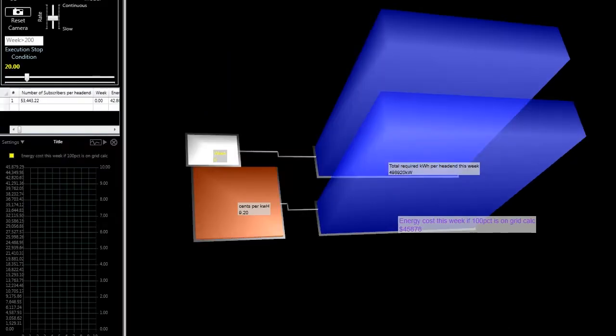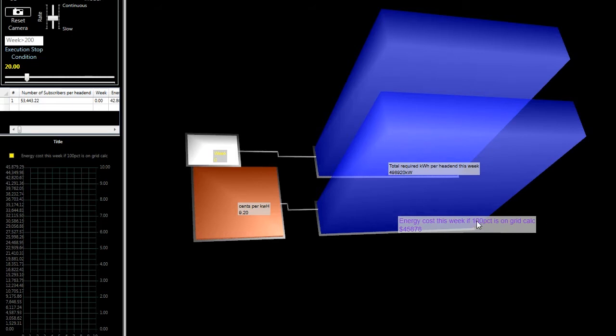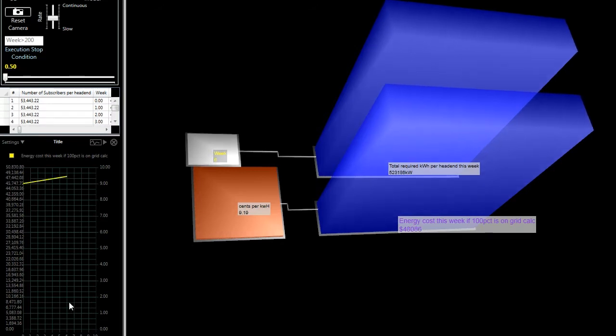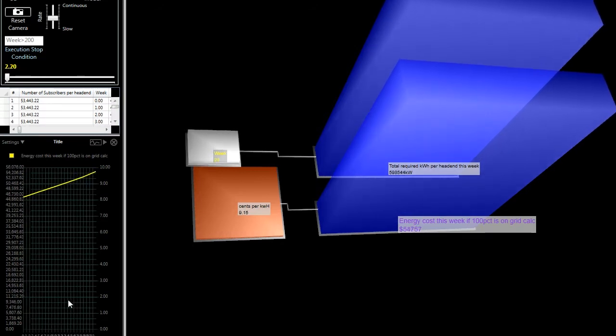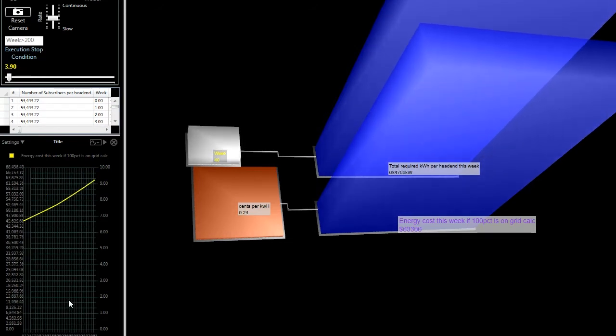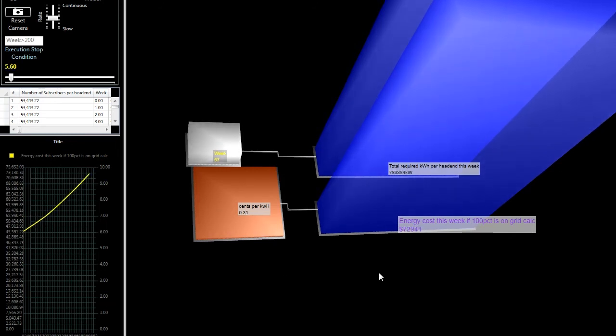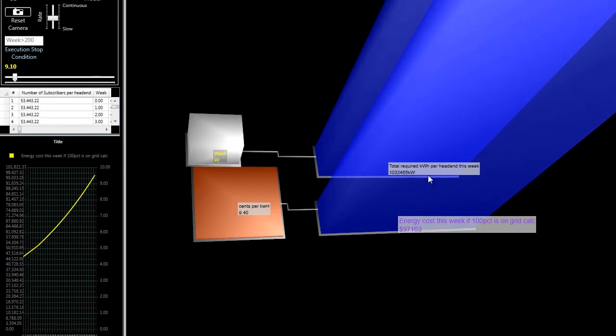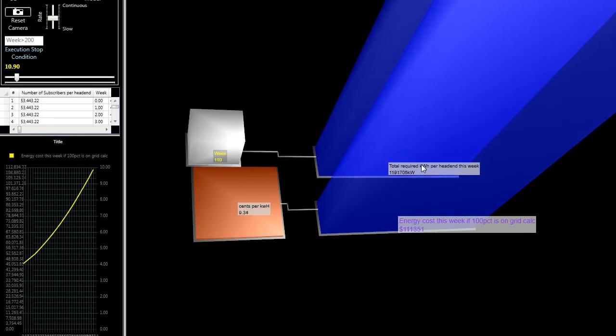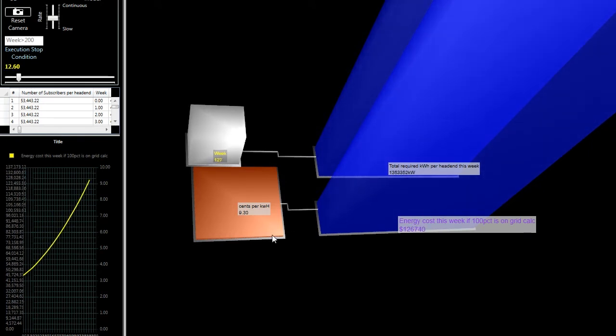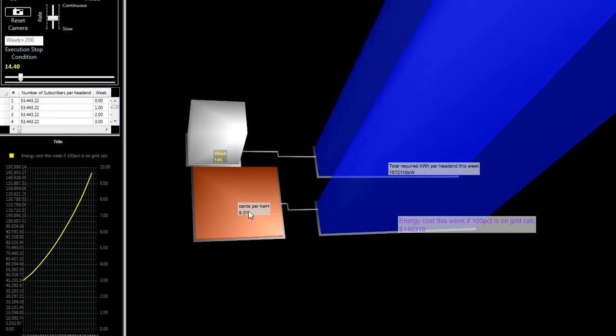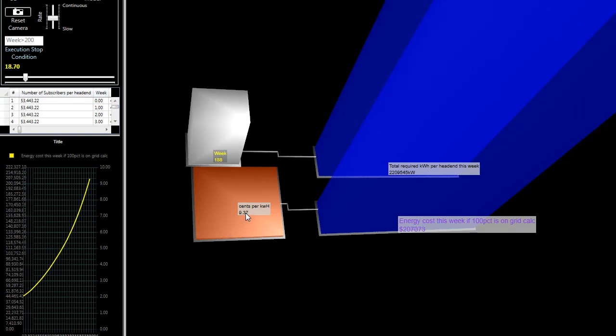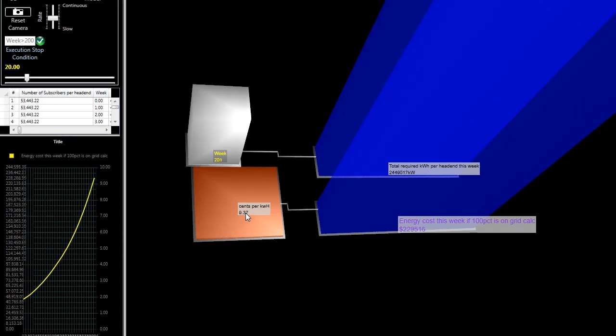You can see at the beginning of the simulation, the cents per kilowatt hours is 9.2. The energy cost for a typical head end we estimated about $45,000. So I've taken this energy cost this week, if all the subscribers at a head end are supplied by grid power, and I'm going to be plotting that. And sure enough, energy costs are going to go up if we use 100% grid power. This is a function of the subscribers going up, the energy per subscriber going up, as well as the cost on a per kilowatt hour basis also increasing over time. So certainly straight grid power looks like it's going to increase considerably, and this is really what's driving the analysis in this video.